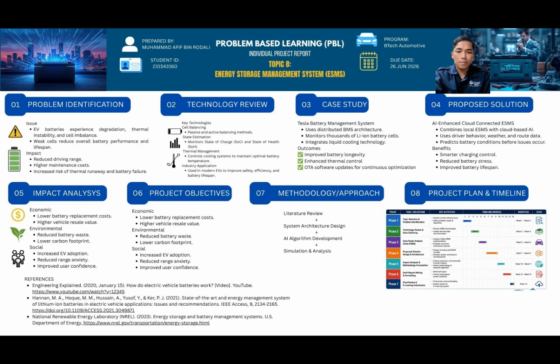Third, thermal management integration. The ESMS continuously reads data from thermistors placed across the battery modules. Based on real-time readings, it controls liquid cooling pumps and fans to keep the cells strictly within their optimum operating temperature window, between 20 and 40 degrees Celsius. High-end EVs today typically utilize distributed topologies using a CAN bus network, allowing a master controller to communicate with multiple slave boards monitoring the cells.